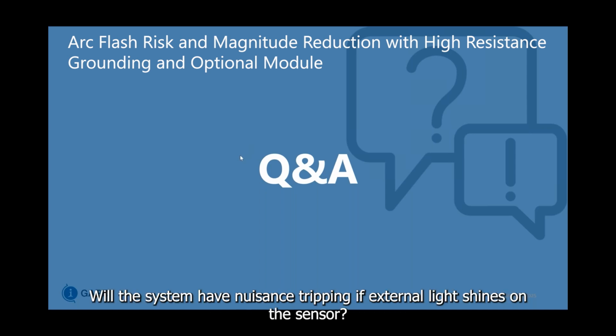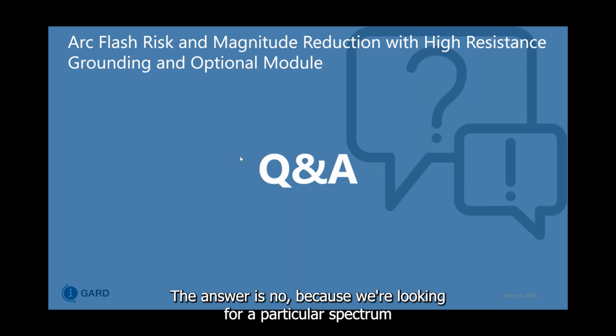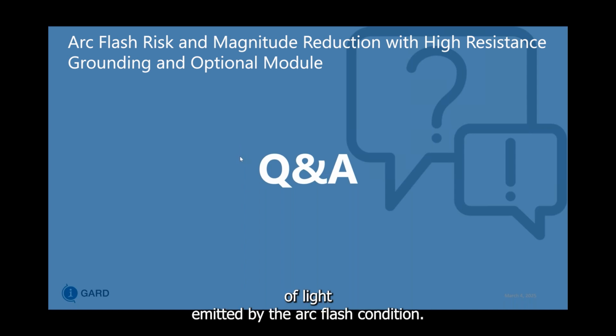Will the system have nuisance tripping if external light shines on the sensor? The answer is no, because we're looking for a particular spectrum of light emitted by the arc flash condition, and that is a very particular spectrum such that we avoid nuisance tripping.